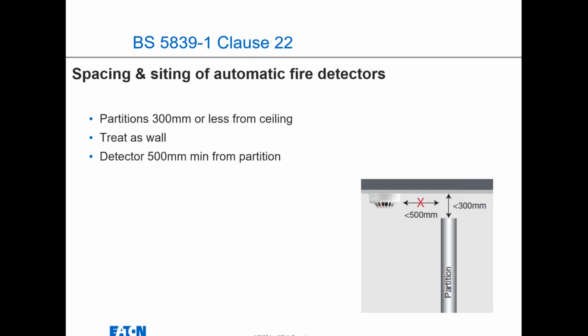The spacing and siting of the automatic detectors: if you've got partitions 300 mil or less from the ceiling, that also needs to be treated as a wall, and the detector again needs to be 500 mil from the partition.